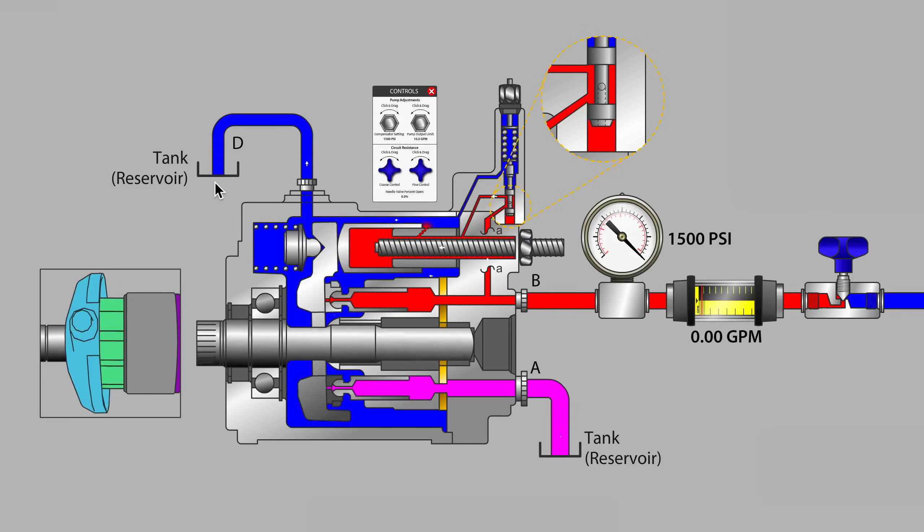And for a very high quality pump at very high pressures that might be in the range of 5%. For some very large pumps it could be up to 10%. And for some very small or very poorly manufactured piston pumps that flow rate could be 15% or more. 15% that is of the pump's maximum output displacement for its regular flow.